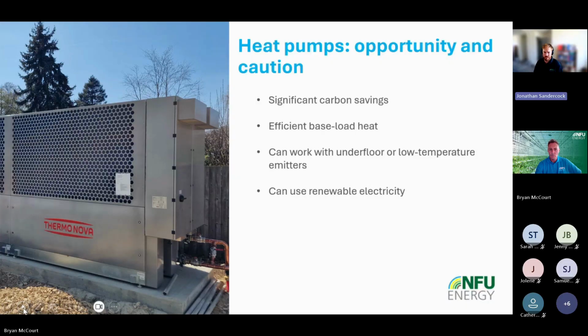And the annual electricity consumption may look manageable on paper, especially if you've got solar or AD to offset that electricity demand. However, the more important question is what happens during the coldest period, especially, for example, solar not being particularly useful in the winter. And if your sheds are all being heated at the same time with your operational management regime, you might find that your grid demand is significantly higher. So as these grid demand connections are currently an area of active reform, standing charges over the next 5 years are getting quite expensive. So switching to a heat pump may trigger the need for a grid connection upgrade, which could then potentially take you into higher banding.